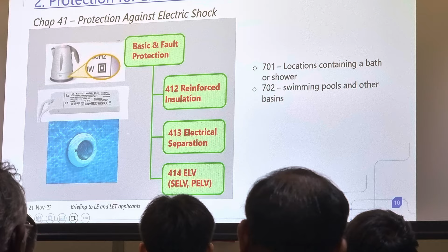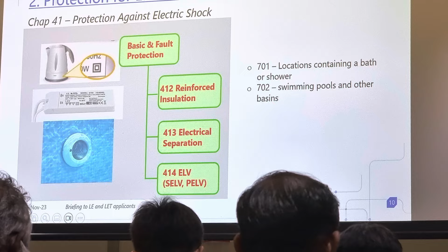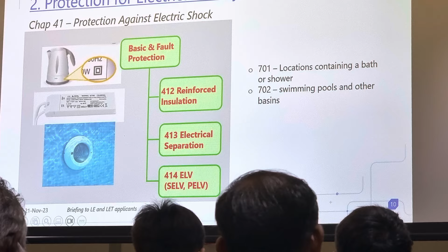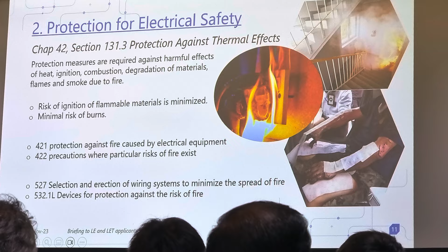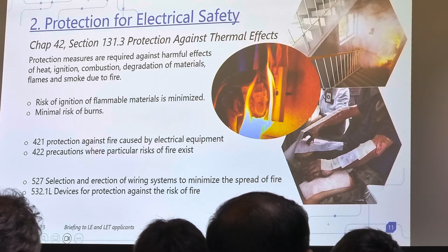So in chapters 41, 43, 44, we read together with chapter 701, where we talk about locations containing bathrooms and swimming pools. Now, the next important thing that we protect against is thermal effects. As I say, when the electrical wires are not properly designed, overloading, there will be fire, there will be arcing. If the design is not done properly, arcing can lead to fire. So, in 638, chapter 42, also in section 131.3, it talks about how to protect against thermal effects.